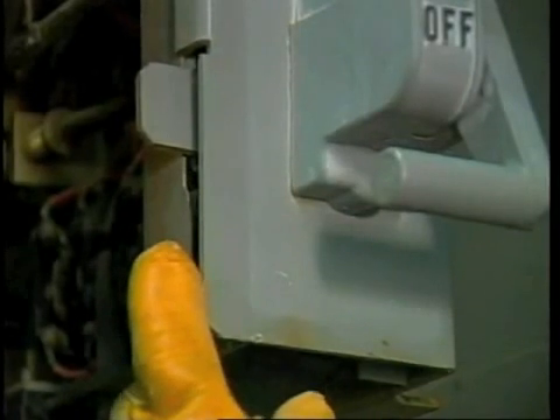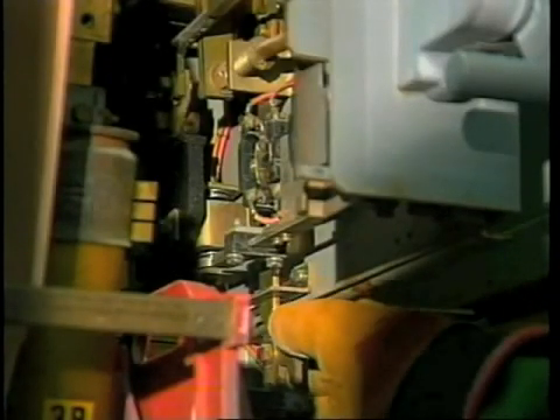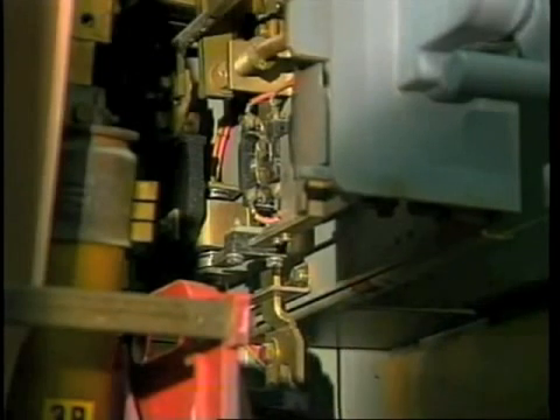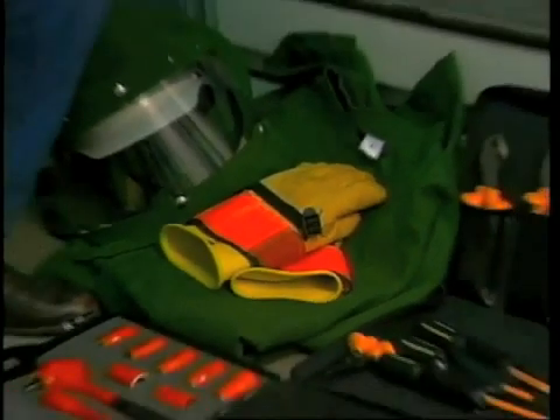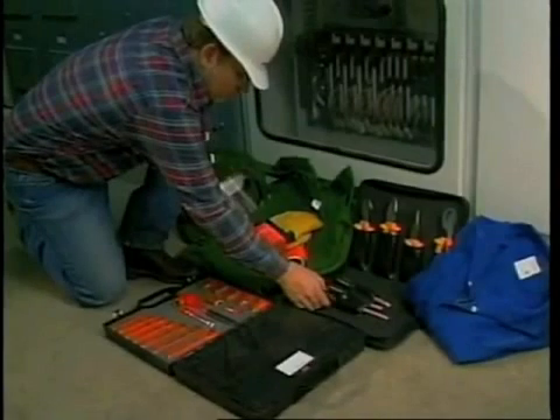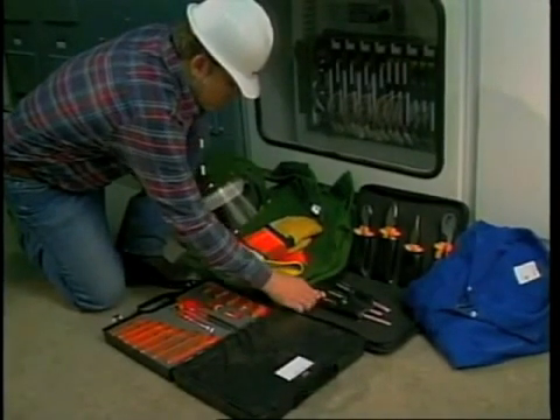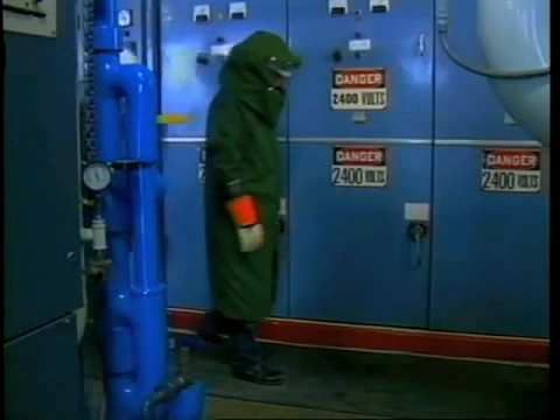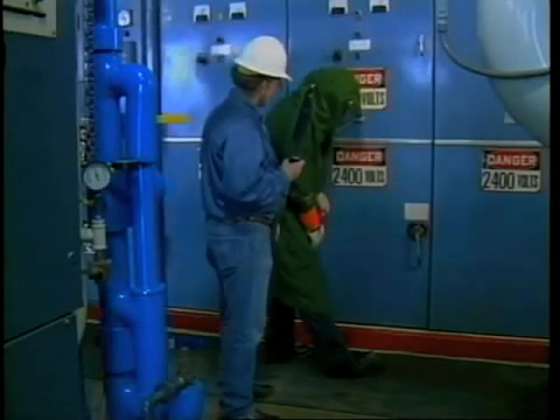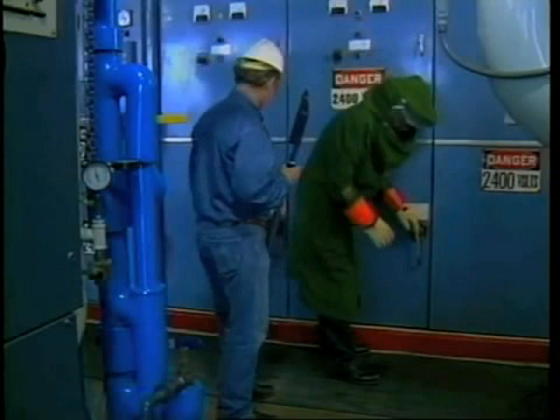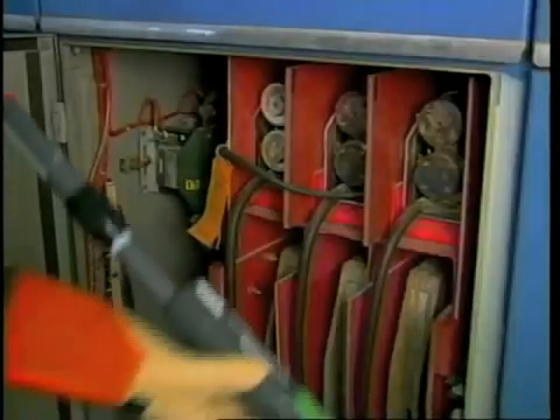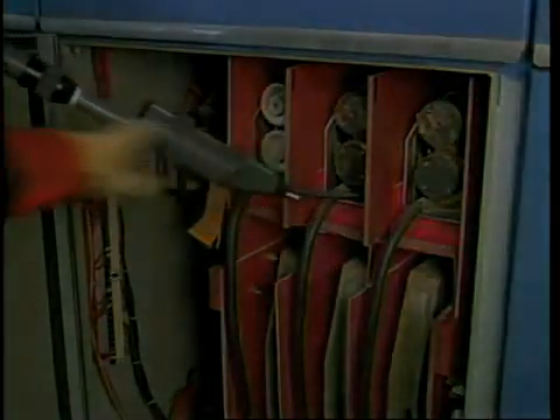These devices are designed to prevent access to the motor control center unless the load side is de-energized first. Identify all electrical interlocks. Electrical interlocks are designed to de-energize the control power if access is attempted without first isolating the motor load. Have all tools and personal protective equipment available and on site before work is begun. Open circuit breakers, fused switches, and contactors before removing or replacing them. Be sure fuses are de-energized before pulling or replacing them.